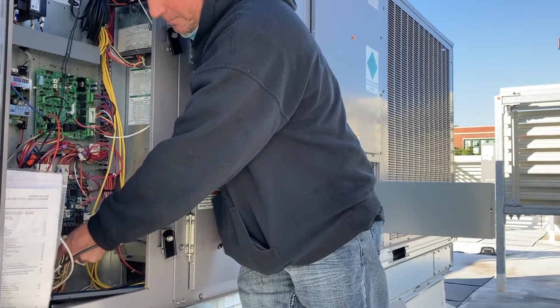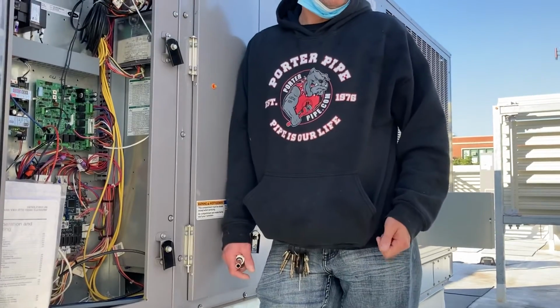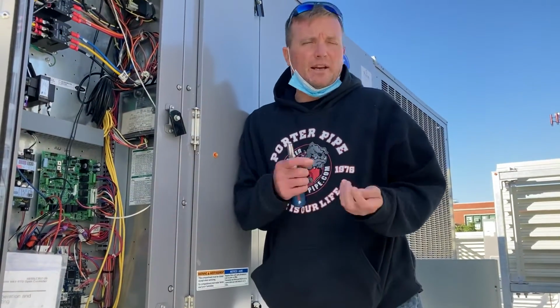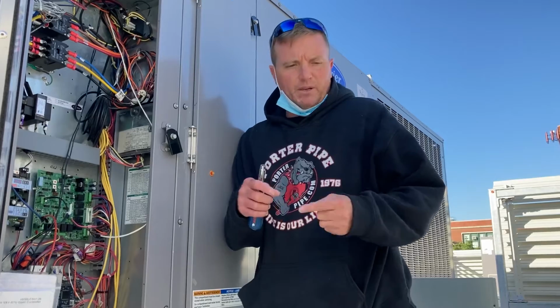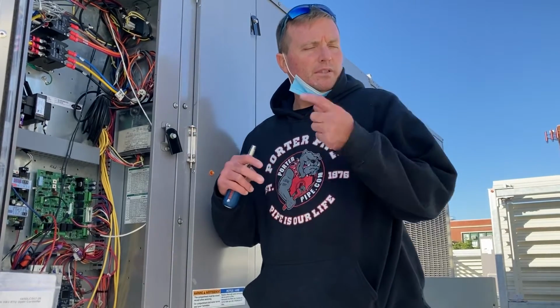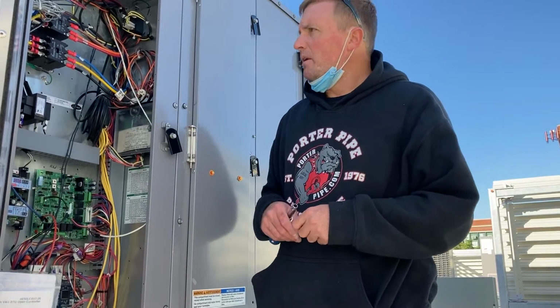Okay, this is 4 to 20 milliamps. So I don't know if you have a milliamp meter or not. You can get one. Basically 4 being stop, 20 being full go. It'll measure it, you know, as far as it's open.